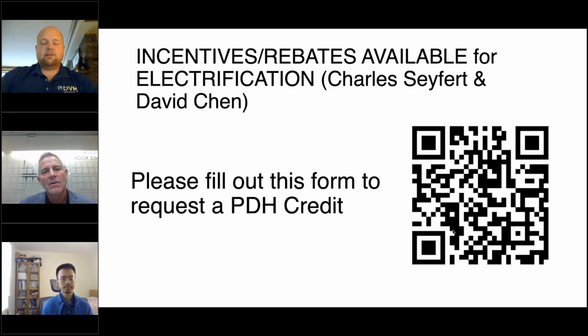Yeah, I'll speak specific to my team. David and I have different focuses for the company, but specific to the electric motor retrofit that my team executes, it is both. There are prescriptive or recommended measures in the different aspects of the laws and codes that do drive those conversations. I mentioned the roof exhaust application - well, that's part of the code. Above six stories, you're required to have mechanical exhaust, and that mechanized exhaust has to run. If you have roof exhausters with broken belts and burnt out motors, then you're in violation of that.